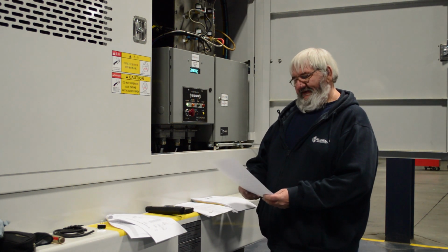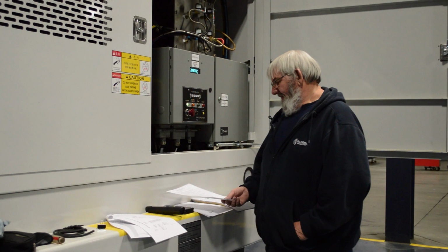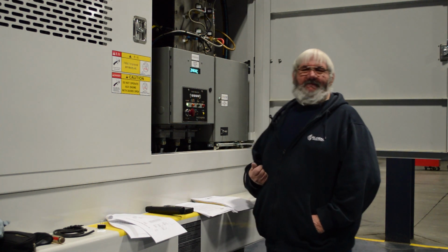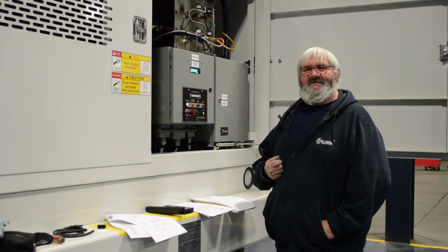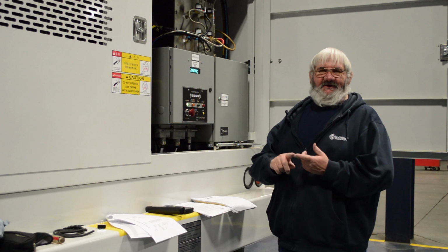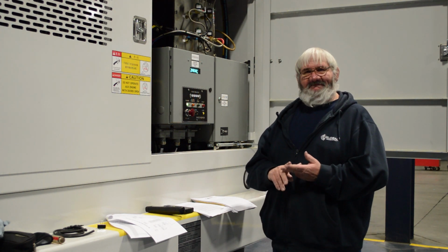Fault code 70, loss of flame. This code indicates that the CAD cell is open when it should be closed. Loss of flame after the heater has been running. Now, typically what you would look for in a fault code 70 is, let's keep it simple, back to the basics. You need air and fuel, but you need the right amount of air and the right amount of fuel to maintain flame.